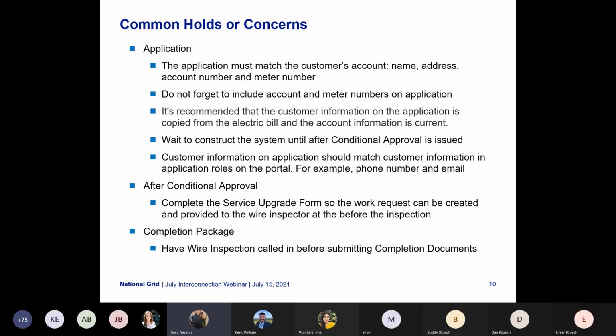Wait to construct the system until you receive the conditional approval. This is important because if you do construct that system before you are granted the conditional approval, and we do check that transformer and that transformer is overloaded, that can cause some voltage issues. So it is very important to wait till you do get that conditional approval to then construct the system.